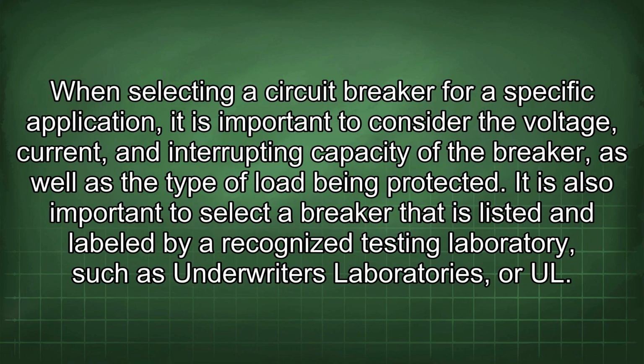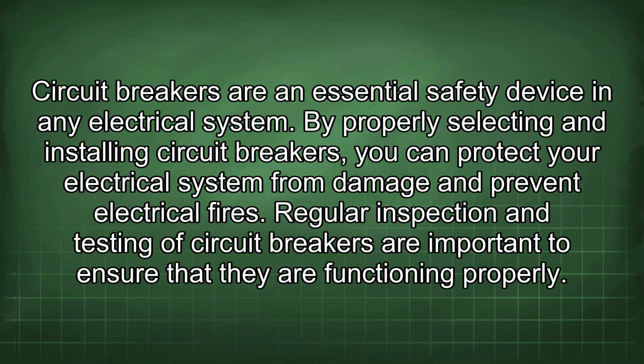When selecting a circuit breaker for a specific application, it is important to consider the voltage, current, and interrupting capacity of the breaker, as well as the type of load being protected. It is also important to select a breaker that is listed and labeled by a recognized testing laboratory, such as Underwriters Laboratories, or UL. Circuit breakers are an essential safety device in any electrical system. By properly selecting and installing circuit breakers, you can protect your electrical system from damage and prevent electrical fires.